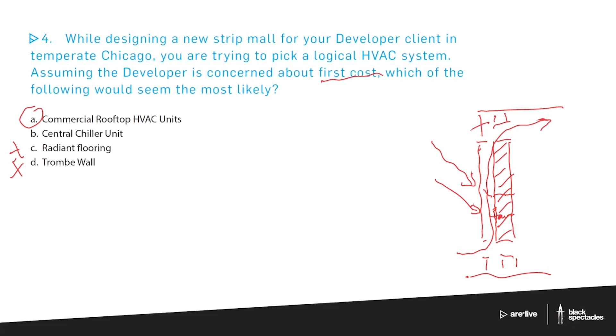The central chiller, that's going to be a classic university building or something. I've been in buildings where the chiller was from the mid-50s and still working great. It's a totally different animal. You tend to use that for whole buildings, whereas in a strip mall you want heating and cooling per individual tenant. So it's about understanding the design implication of these few words in the question. What does it tell me? It tells me strip mall, which means individual tenants and fairly high turnover. First cost tells me we're worried about low first cost — we're not trying to build a Cadillac system meant to last 100 years. When you think it through with those lenses on, A really becomes the only logical answer.